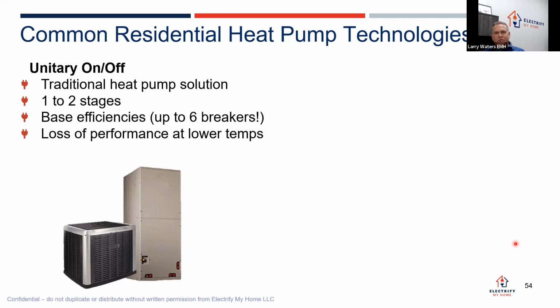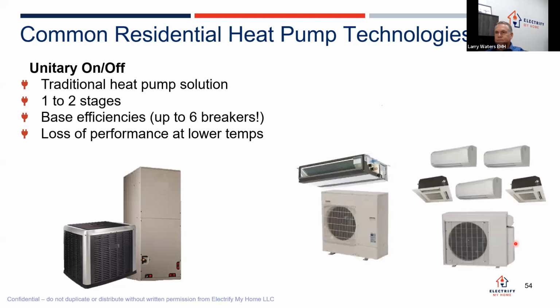Most of the time, those are going to need some sort of a backup heating source, because heat pumps lose their efficiency when it gets cold outside. It's a refrigeration cycle, and when the air coming into the heat pump is too cold, the unit can't give you the amount of heat out the other side. So there's a couple things that contractors that install a lot of these do. They either oversize them, so when it gets cold, they still have plenty of capacity, which means they're grossly oversized for when it's mild outside, or they have to put in a backup heating strip or connect it to another furnace. See that a lot too, which is not good electrification.